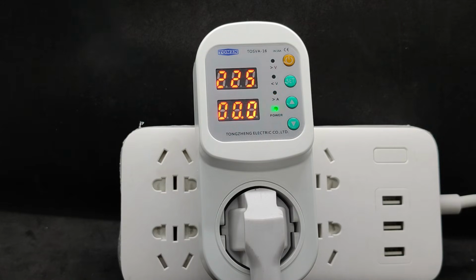At the moment, the load is not connected. The relay is operating. As soon as I turn on a load whose current is higher than the set value, the relay turns off after 0.1 seconds. Now another LED lights up for overcurrent. Since current cannot be measured without a load, the relay will turn on every 10 seconds. Since the current is still above the threshold, it will immediately turn off. By default, it will do this continuously, so you can set the number of attempts. And if the excess load is removed, the relay will restore its operation.